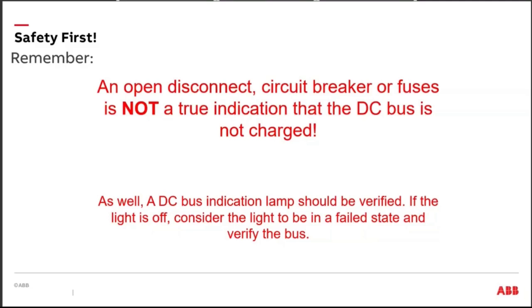On all drives, there's a DC bus indication lamp. It just says a little lamp that comes on that says DC bus charge. And you would think that when that light goes off, the bus is no longer charged. If you're going to be the person putting your hands inside that drive, assume that the light has failed.